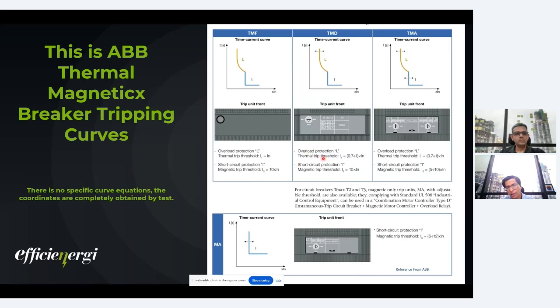Then there is another thermal magnetic unit where you can adjust the thermal trip units, but the magnetic trip is again fixed. And there is a third one wherein you adjust the thermal trip as well as the magnetic trip. So these are the three kinds of trip units that we can see in thermal magnetic.